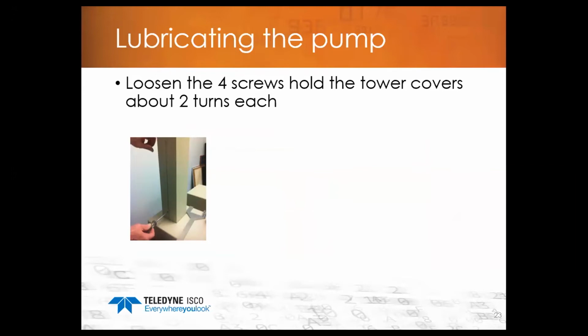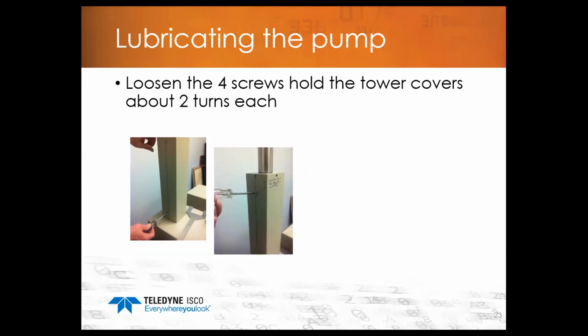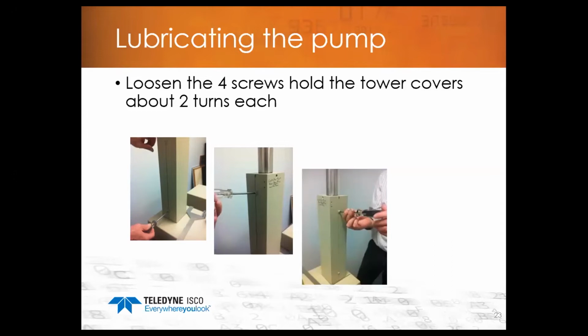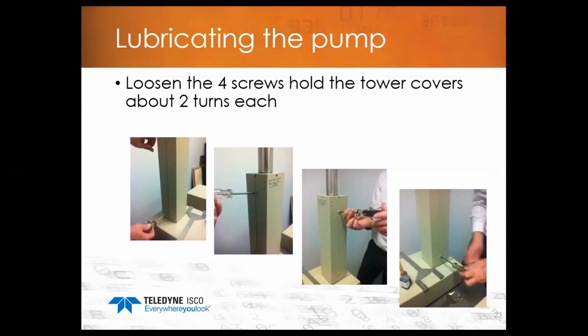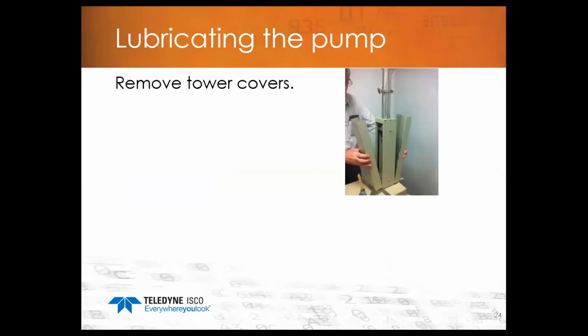There's two tower covers on the pump, and they're secured with 2 screws on each side. You just loosen those 2 screws on each side, and then that will allow you to remove the 2 tower covers. And then the 2 tower covers come apart, and that will allow you to have access to the ball screw, which, at this time, with the pump in the empty position, will be fully extended.